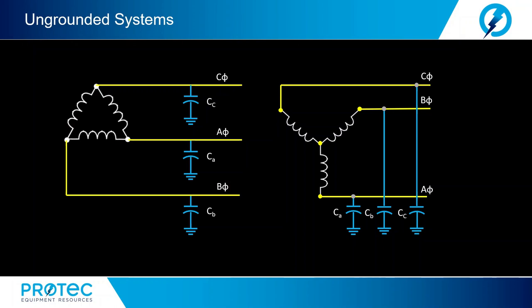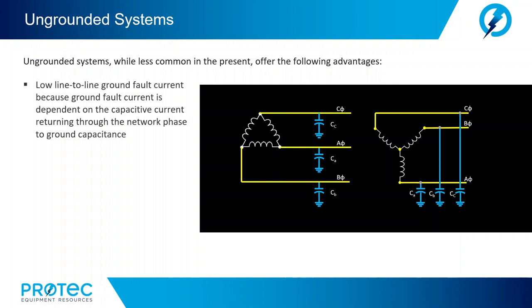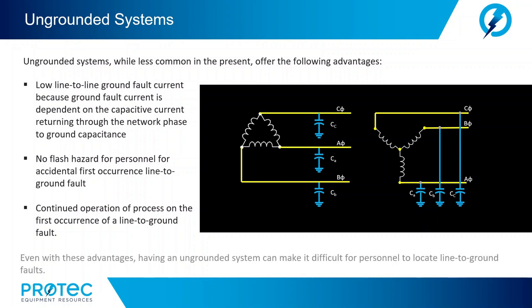Ungrounded systems, while less common today, offer the following advantages: low line-to-ground fault current because ground fault current is dependent on the capacitive current returning through the network phase-to-ground capacitance; no flash hazard for personnel for accidental first occurrence line-to-ground fault; and continued operation of processes on the first occurrence of a line-to-ground fault. However, having an ungrounded system can make it difficult for personnel to locate line-to-ground faults. It also places personnel at risk during maintenance and offers little control over transient overvoltage.